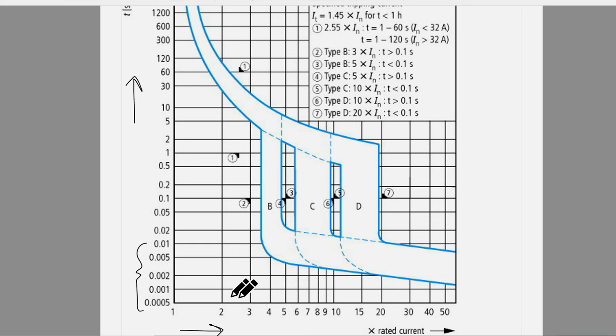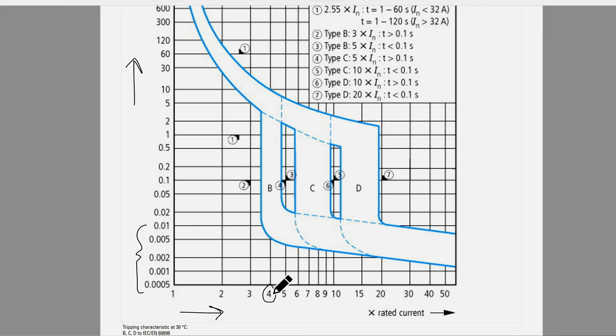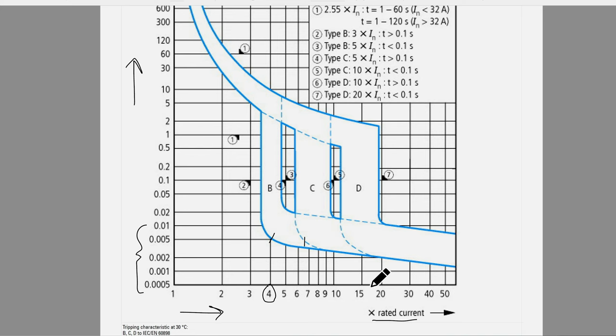If we have a current that is four times the rated current — say 40 amps on a 10-amp breaker — and that current lasts five milliseconds, a circuit breaker following a B curve would most probably trip. But if the circuit breaker followed a C curve, it could allow for about six and a half times the rated current before tripping. This means that with a C curve breaker you could effectively have more floodlights, keeping in mind that LED floodlight inrush can be at least 10 times and even over 100 times the nominal current.